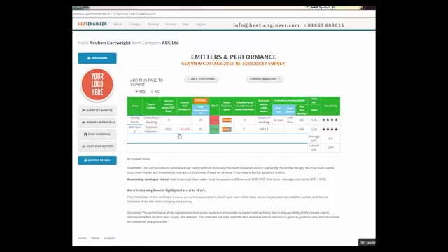So you'll recall that we entered a radiator, I think it was a K2 radiator for bedroom 1, and what it's done is worked out the undersize factor. So it's undersized by 16%, and of course what we do here to work out the oversized factor is we times the room heat loss by, in this case, 3.1, which is dictated by the flow temperature, and the output required is just over 1900 watts. So we're all happy with this anyway for the report.